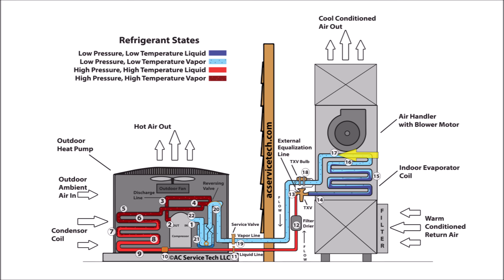In step seventeen, you have the low pressure, low temperature vapor refrigerant continuing to absorb heat and increasing in temperature — the refrigerant is in the process of superheating. In step eighteen, you have the low pressure, low temperature, superheated vapor exiting the evaporator coil. The amount of temperature increase between where the refrigerant comes out of the saturated state at step sixteen and where it exits the evaporator coil at step eighteen is called the superheat.